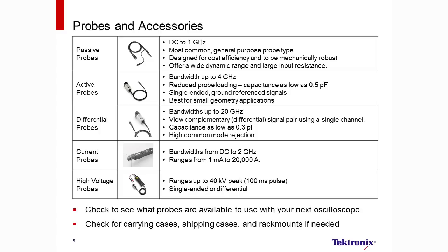Our probe design engineers like to say that an oscilloscope is just a display for probes. This doesn't impress our scope engineers much. But the fact remains that probes are a critical part of the system. Check the probing alternatives for any scope you're considering. In today's scopes, the instruments and probes can communicate with each other. This allows the scope to not only sense the right scale factors, but it also lets you change factors or ranges on the scope front panel. The scope can tell you right on the screen when a current probe jaw is open, and it can guide you through procedures like current probe degaussing.